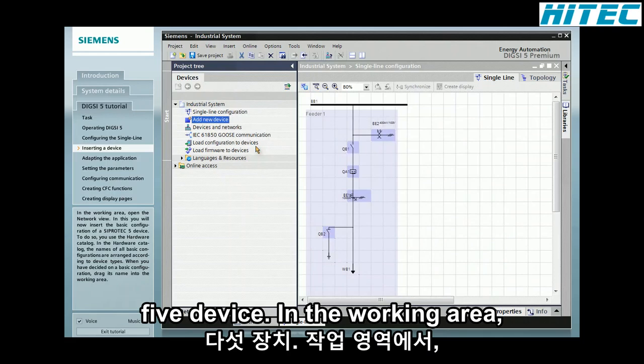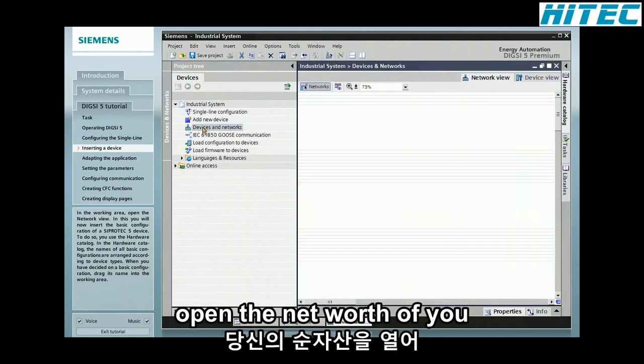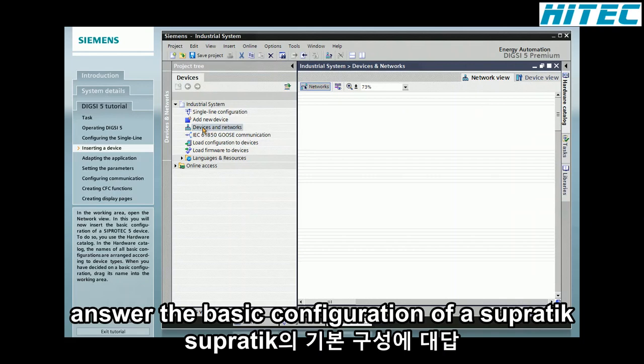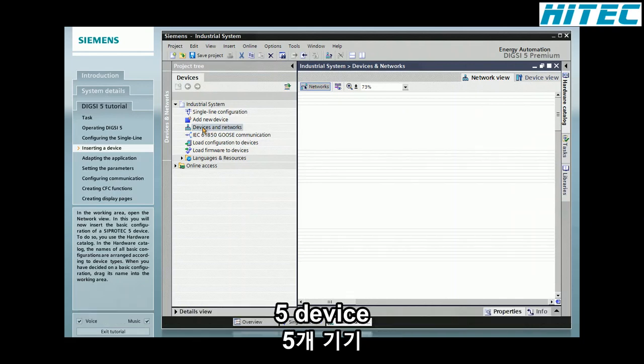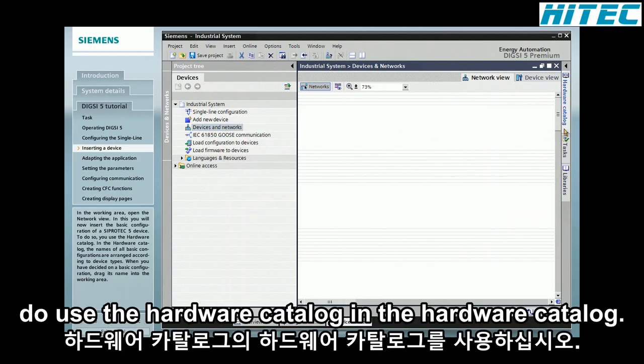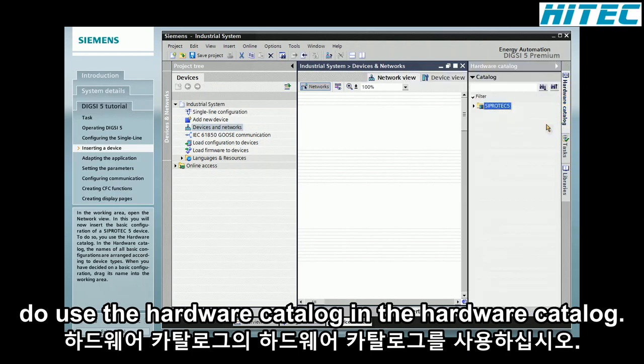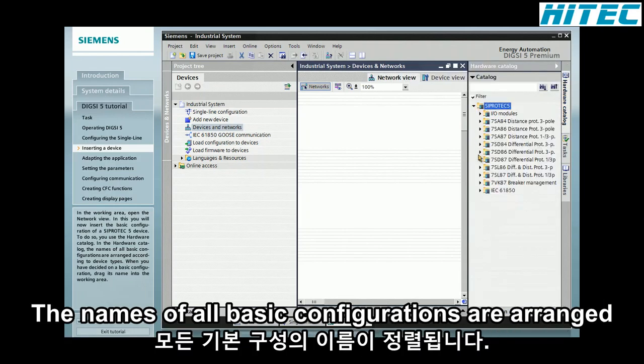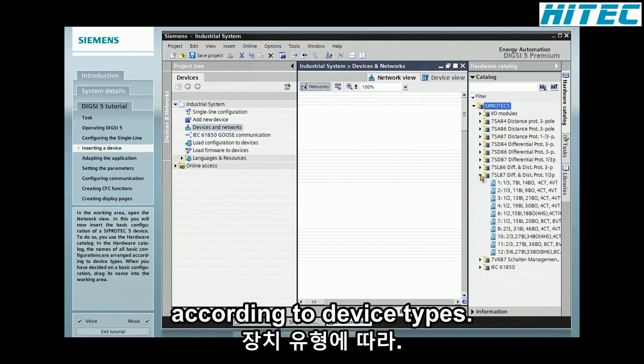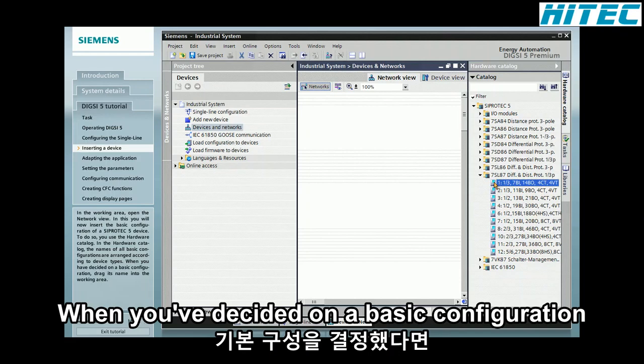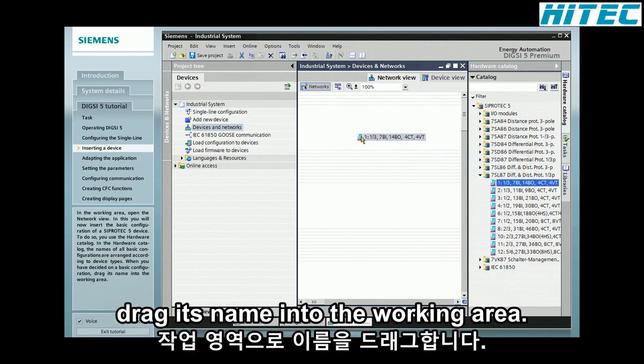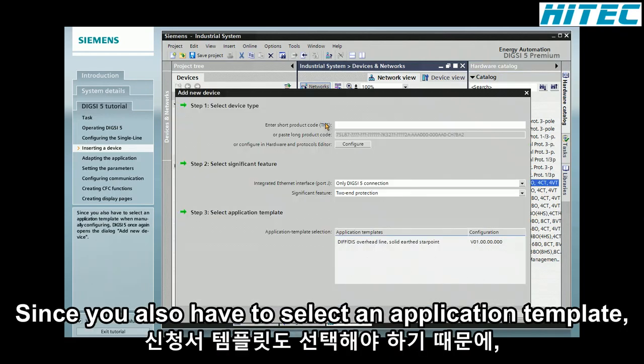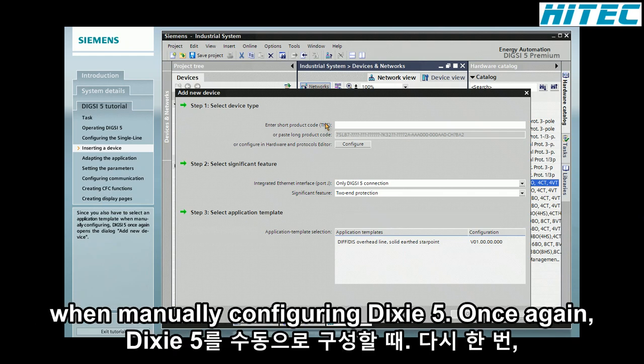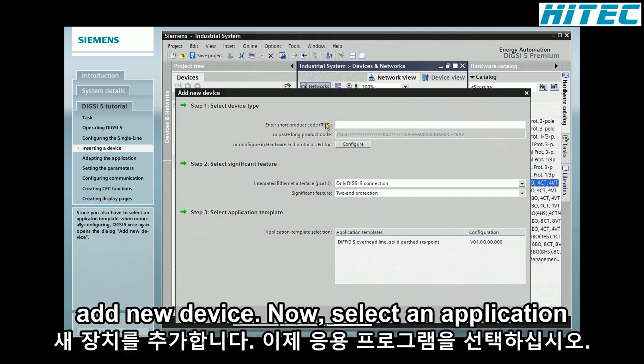In the working area, open the Network view. In this, you will now insert the basic configuration of a SIPROTEC 5 device. To do so, you use the Hardware Catalog. In the Hardware Catalog, the names of all basic configurations are arranged according to device types. When you've decided on a basic configuration, drag its name into the working area. Since you also have to select an application template when manually configuring, DIGSI 5 once again opens the dialog Add New Device.